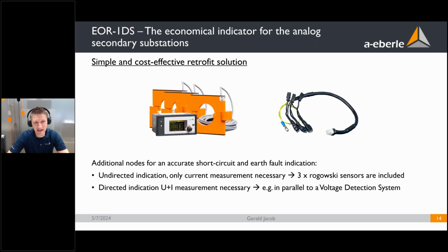As you can see here on the left side, the indicator can be ordered directly with 3 of these current sensors. These are Rogowski sensors that can be mounted easily around the medium voltage cable and connected to the indicator EOR-1DS, and then you have an undirected short circuit indication, and also a pulse location is possible. If you install in addition also a measurement for the voltage, for example with this adapter cable on the right side that you can connect in parallel to a CAPTIS or Vega device, so voltage detection system device, VDS device, then you have a voltage measurement, you have a current measurement, and you have the possibility to have a directed indication of earth fault and short circuit.